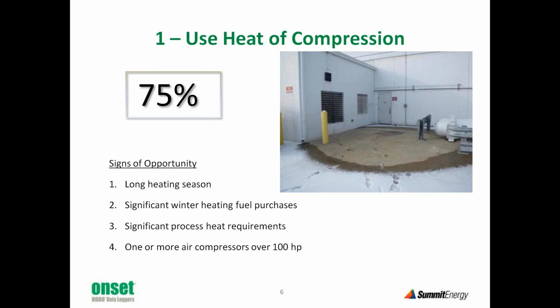So the number one suggestion for reducing energy use, use the heat of compression. How many of you have an area that looks like this picture on the right? It's great for smokers that aren't allowed in the building. It's a nice warm spot near the building. But for an energy manager, this is an opportunity. What's actually happening here is warm air from an air compressor on the other side of the wall is being exhausted to the outside in the winter, creating this nice warm spot.